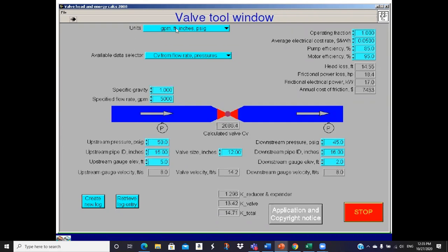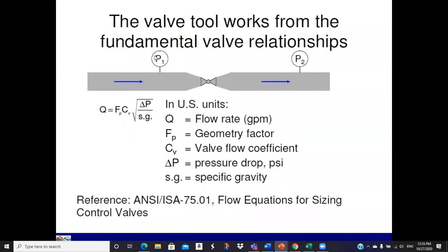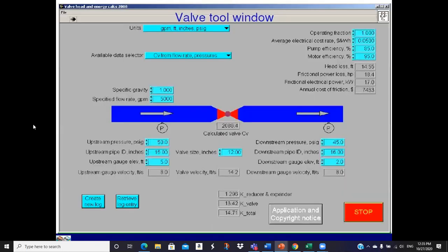We can set units, it's got 3 or 4 different systems of units you can operate in. And then we basically have 4 inputs. We have flow rate, 2 pressures, and a CV. If you look back at this equation, what do we have? This is just a geometry factor, so it's a direct calculate. It doesn't count as one of the variables. So you've got Q, CV, P1, and P2. That's all you've got. So this is a pull down, and it gives you 4 options.